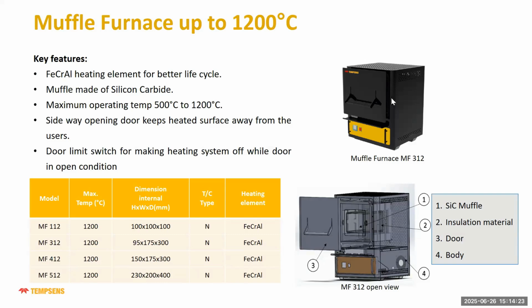It is an advantage that we use a silicon carbide muffle. Silicon carbide has an advantage over the ceramic muffle: its thermal shock resistance is far better than the alumina muffle. So when you want to open the furnace at high temperature, or heat continuously for 7 or 8 days, you can use this silicon carbide muffle. The operating temperature can be from 500 degrees centigrade to 1200 degrees centigrade.